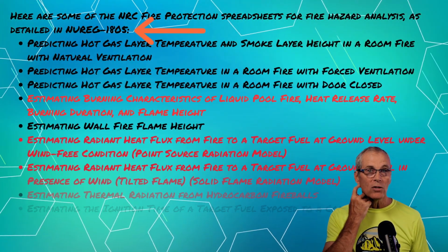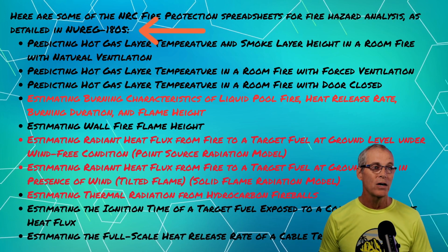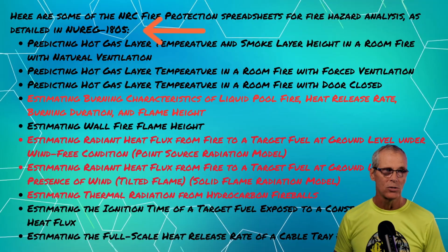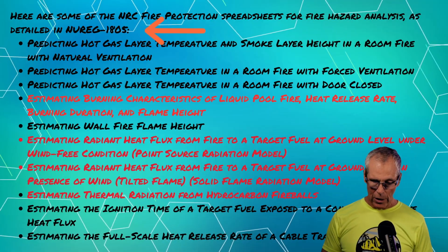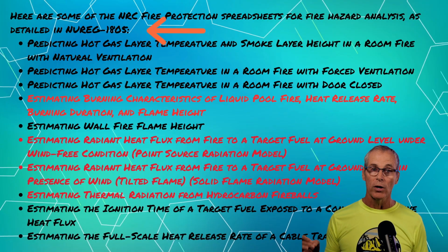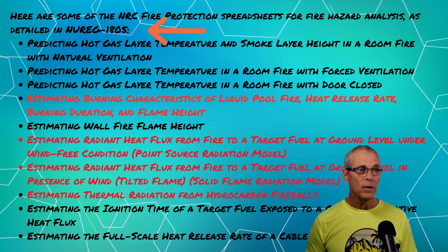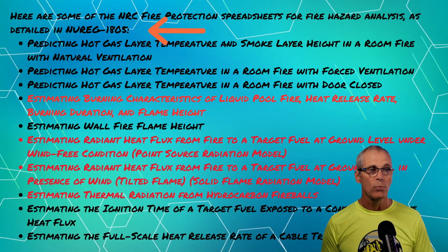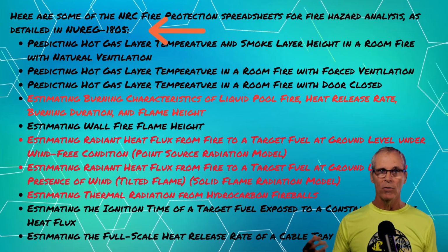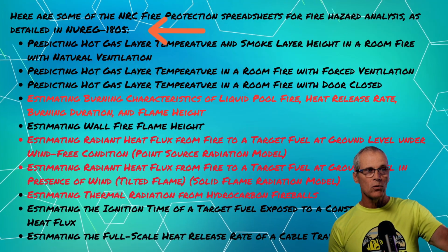The Nuclear Regulatory Commission has a fantastic document, NUREG-1805, and if you Google that, I'll give you the link to it, but it's probably easier just to Google that. But you see that they have many of these calculations. They've got actual spreadsheets, live working spreadsheets you can download to run these kind of calculations. Estimating the burning characteristics of liquid pool fire. How many of us have that in chemical industry, in the power industry, transformer pool fires, right? We can calculate now the heat release rate, the burning duration.